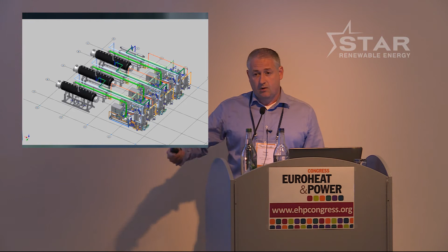The significant thing though is, because the heat pump's a very flexible device, they're actually getting about 85% of the heat from this energy centre from the heat pump and only 15% from the top-up gas. So we might well have to keep using fossil fuels of some sort, but at least it's only going to be a small component. We played a couple of tricks with this that are worth mentioning. We actually have 3 heat pumps in series. One is heating to 90, one is heating to 80, and one is heating to 70. We also have 3 heat exchangers for the seawater, which are titanium and tube design. So it's very easy to clean them, and they're able to give us a very high performance with a very, very low charge of working fluid.